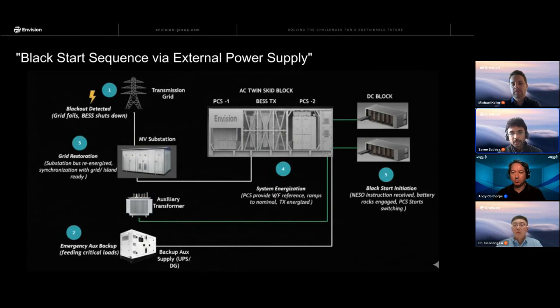And with this, we get all the critical loads fed from the emergency system, and then we start engaging the DC rack contactors of the battery racks, and then the DC bus will be charged, and the PCS will need to start in the grid forming mode, providing the voltage and frequency reference. And again, we energize the transformer, which will in turn energize the substation, and basically we restore some part of the transmission system.